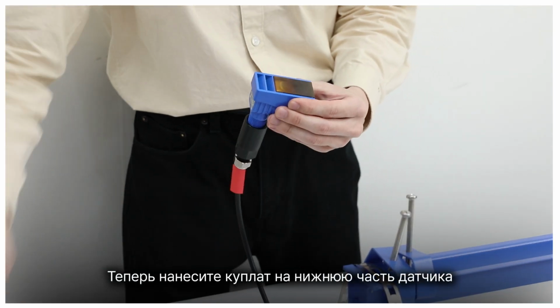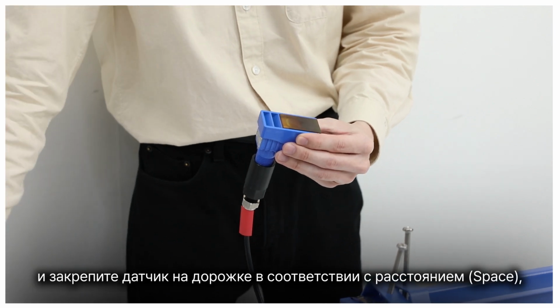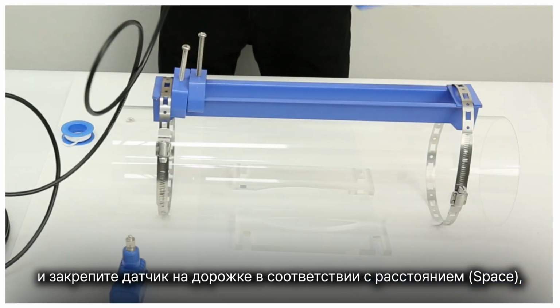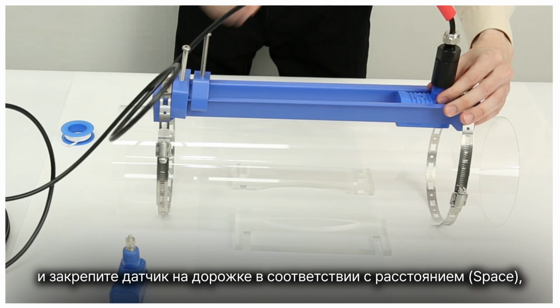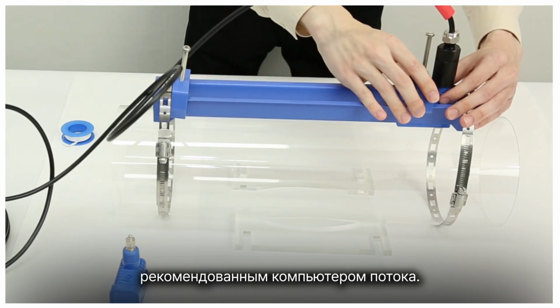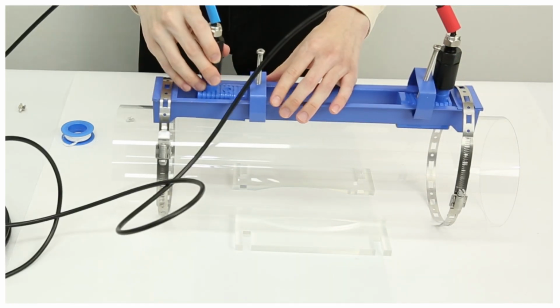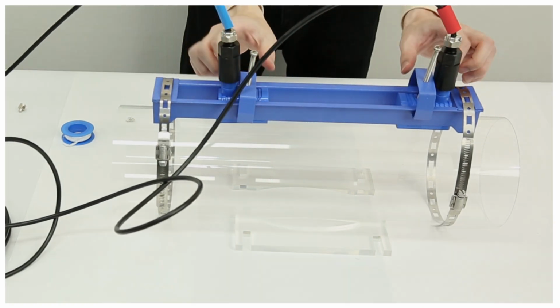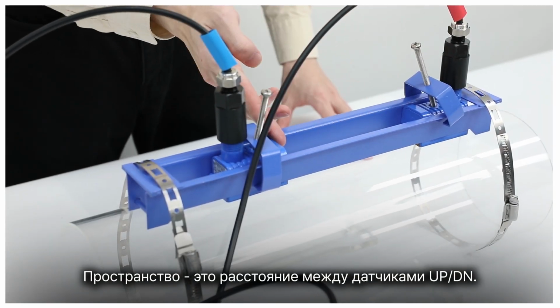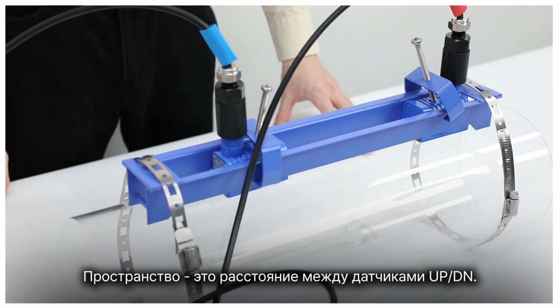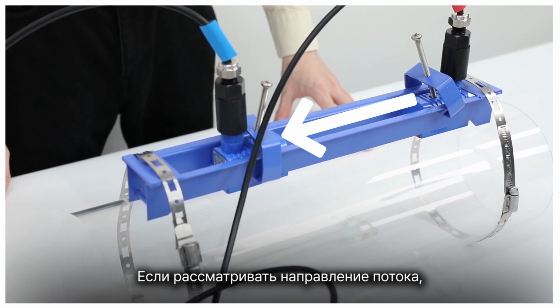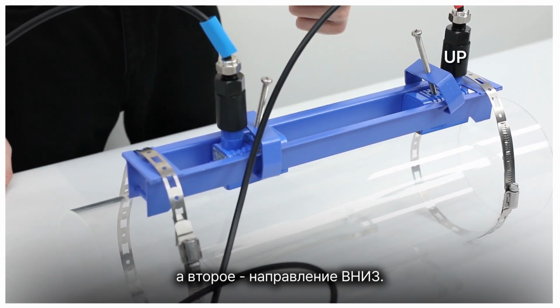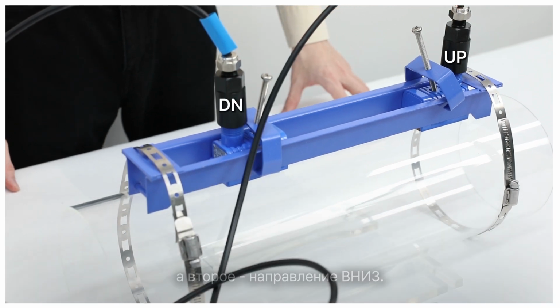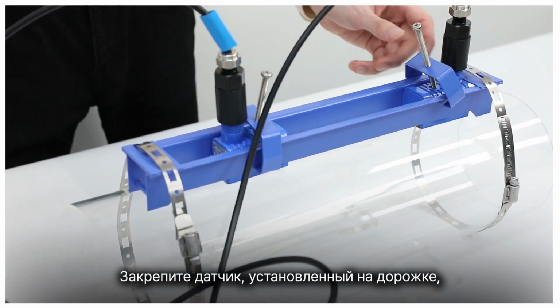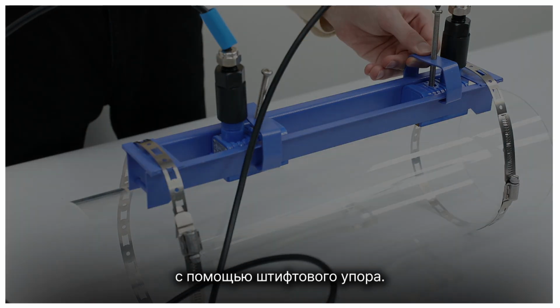Now apply couplant to the bottom of the transducer and fix the transducer in the track according to the distance or space recommended by the flow computer. Space is the distance between the up and down transducers. Considering the flow direction, the first is up and the latter is down. Fasten the transducer installed in the track with a pin stop.